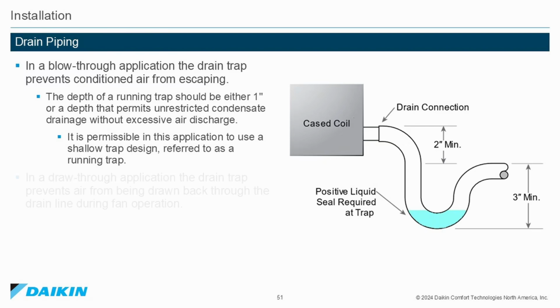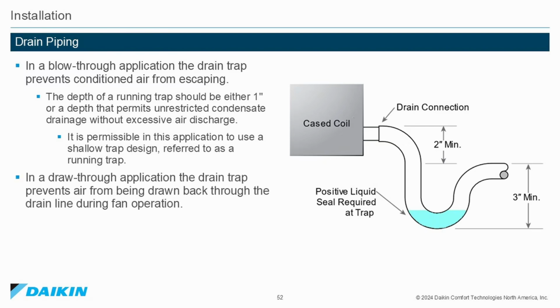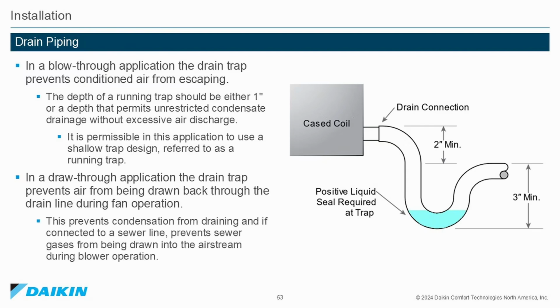In a draw-through application, the drain trap prevents air from being drawn back through the drain line during fan operation. This prevents condensation from draining, and if connected to a sewer line, prevents sewer gases from being drawn into the airstream during blower operation.